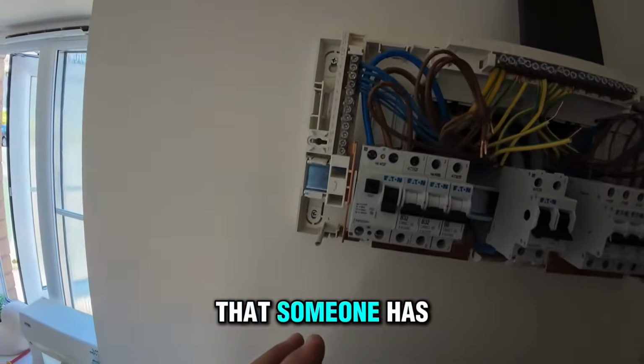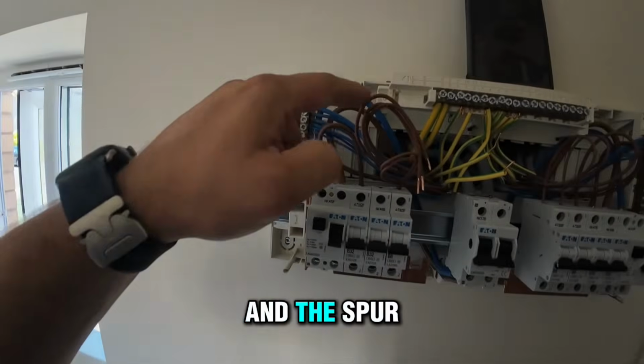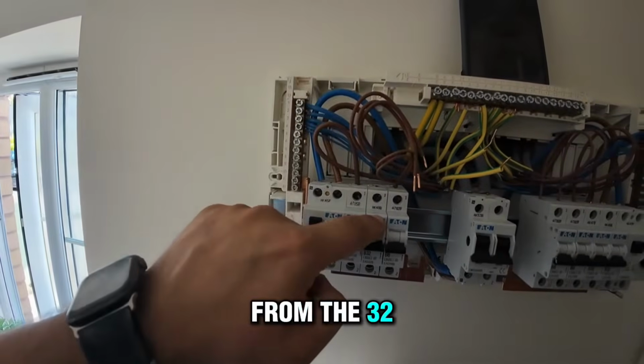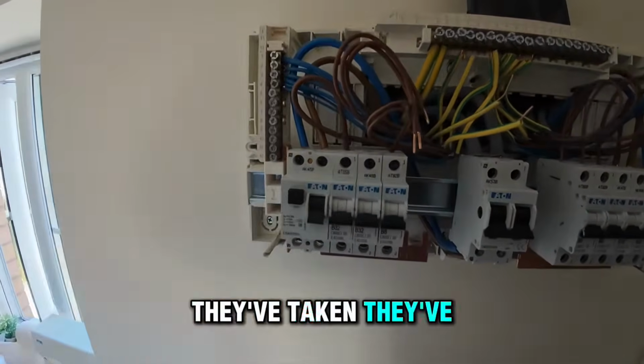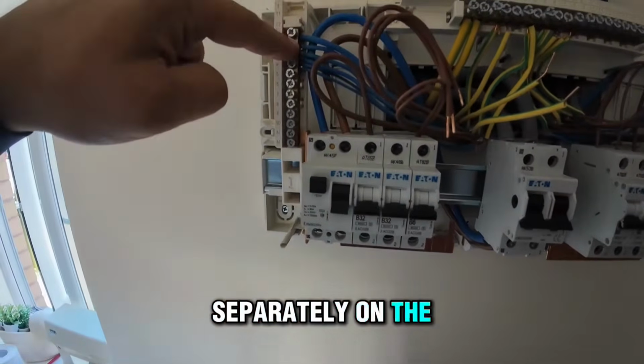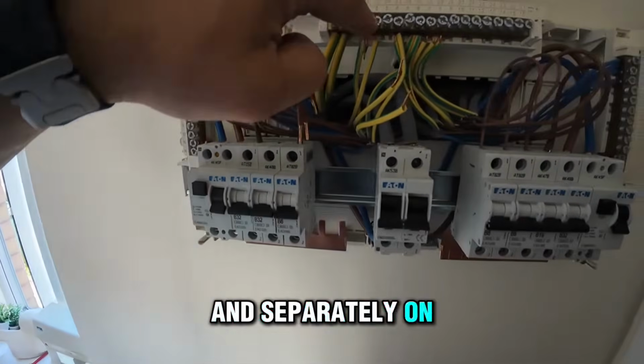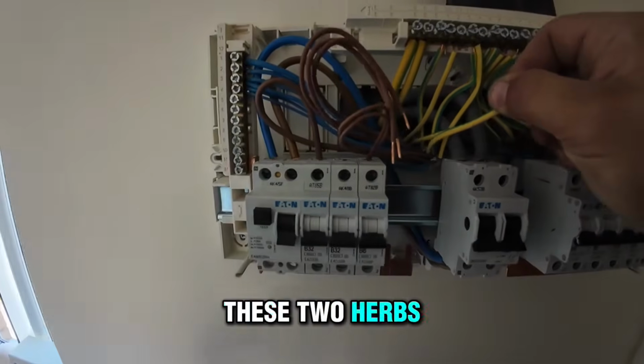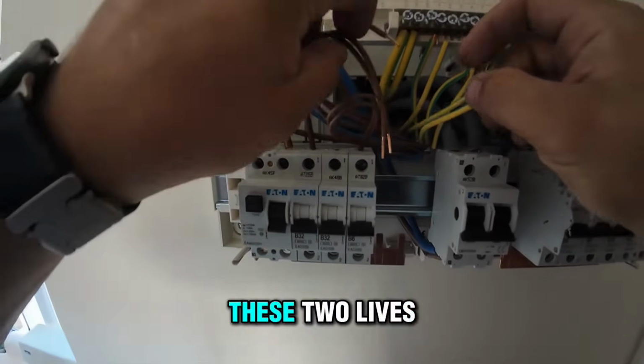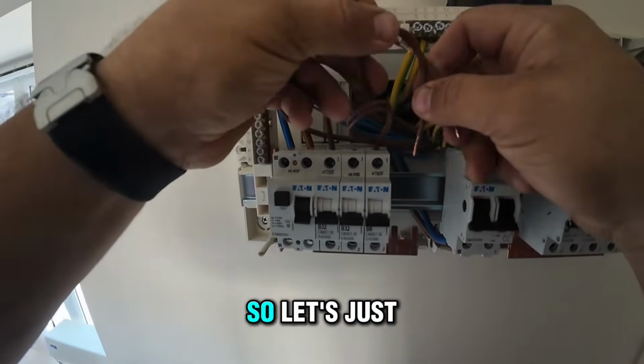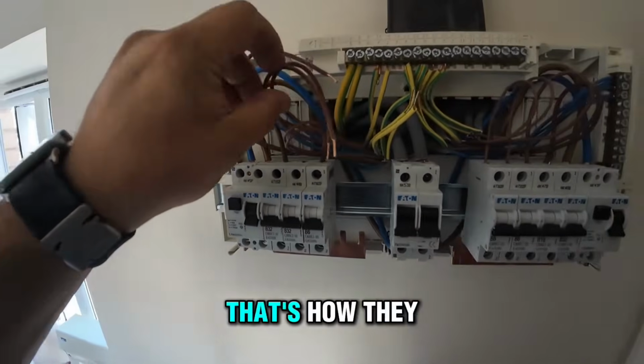I can see that someone has thought about it, and the spur from the 32 circuit breaker they've taken, they've actually put it separately on the neutral bar and separately on the earth bar. These two earths would correspond to these two lives. So let's just double check if that's how they did it.